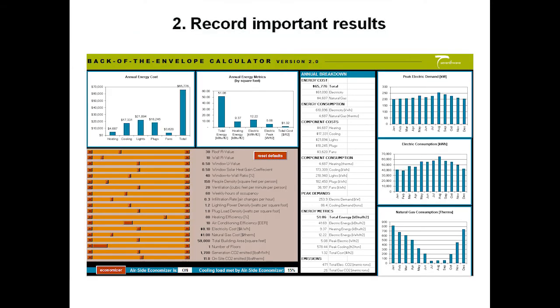Now that we have the baseline building parameters input, we want to record our important results. What are the important results? Often it's cost, but that question is really up to you. The important results that I've recorded here include the annual energy cost, annual electric consumption, natural gas consumption, peak electric and cooling demand, and total CO2 emissions. It's often helpful at this point to do a quick sanity check to make sure these values make sense. The annual energy cost comes out to about $1.40 per square foot, which is well within the acceptable range for an office. You can also cross-check the consumption rates against CBECS published data from the Department of Energy.